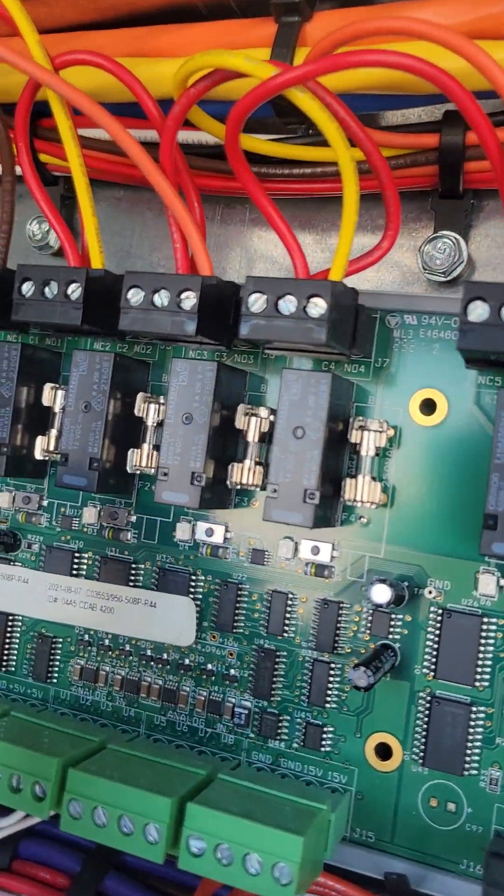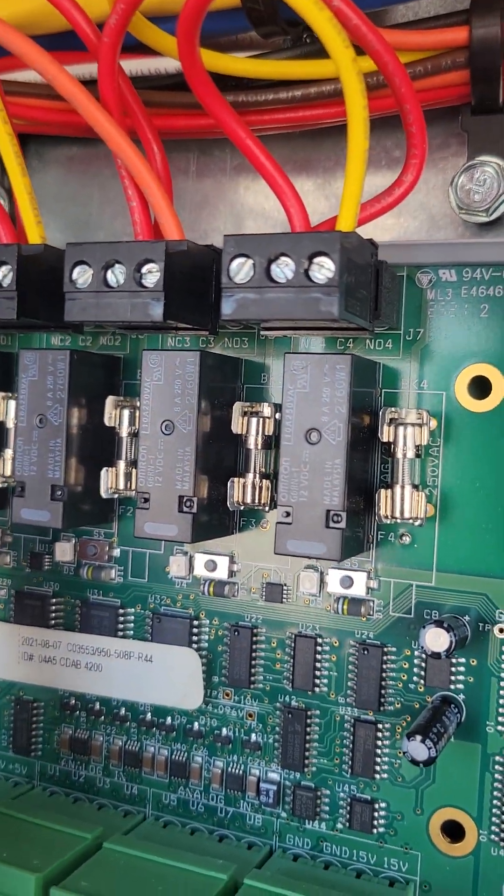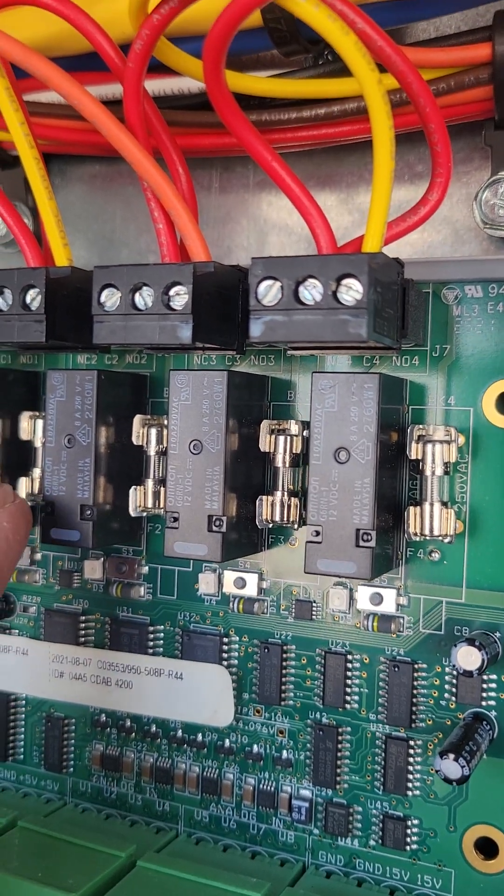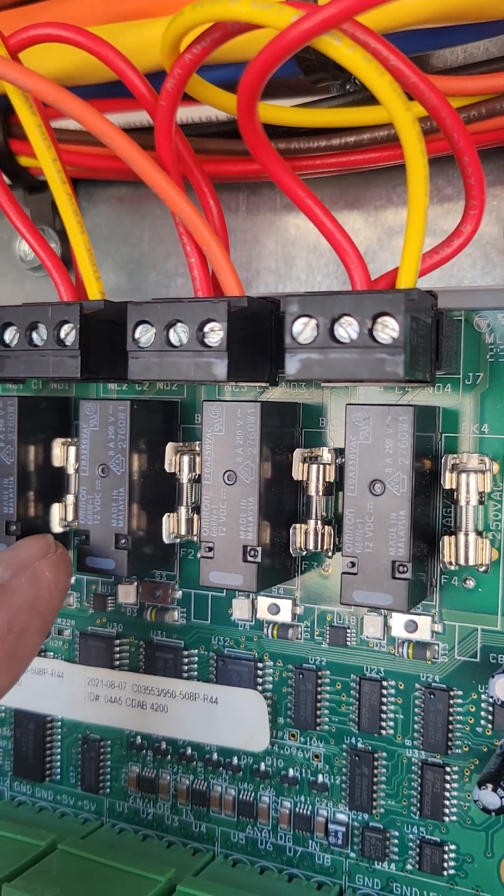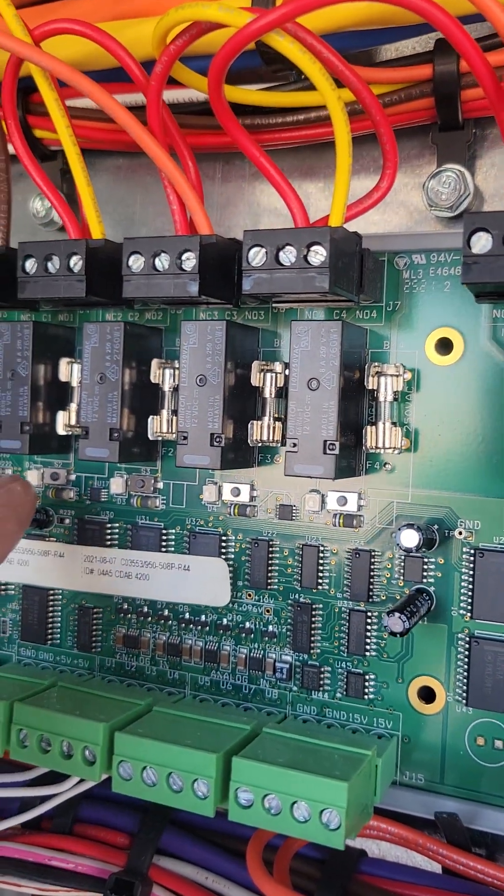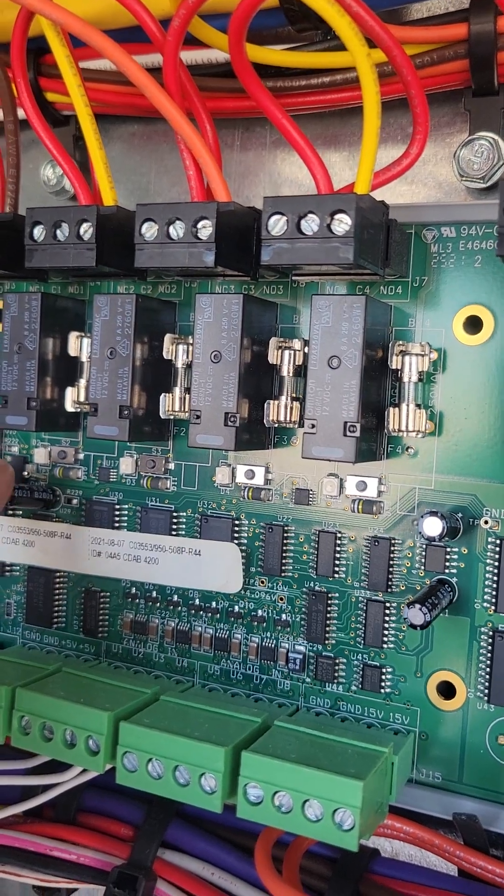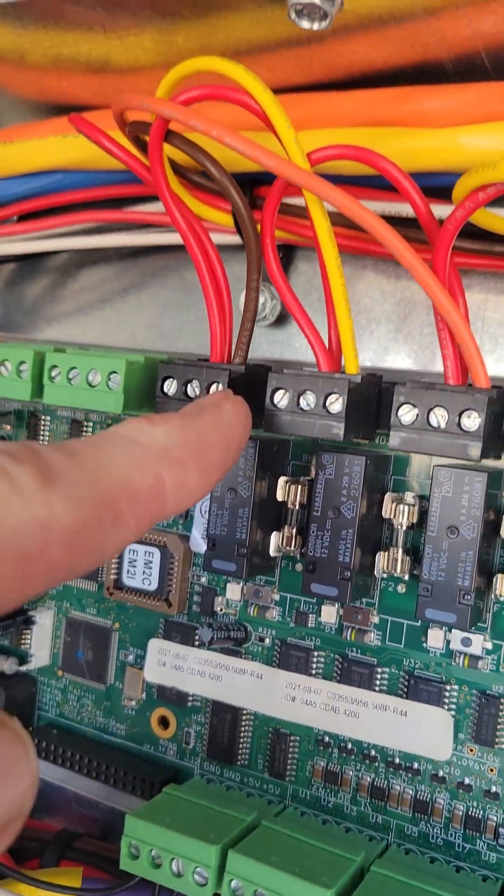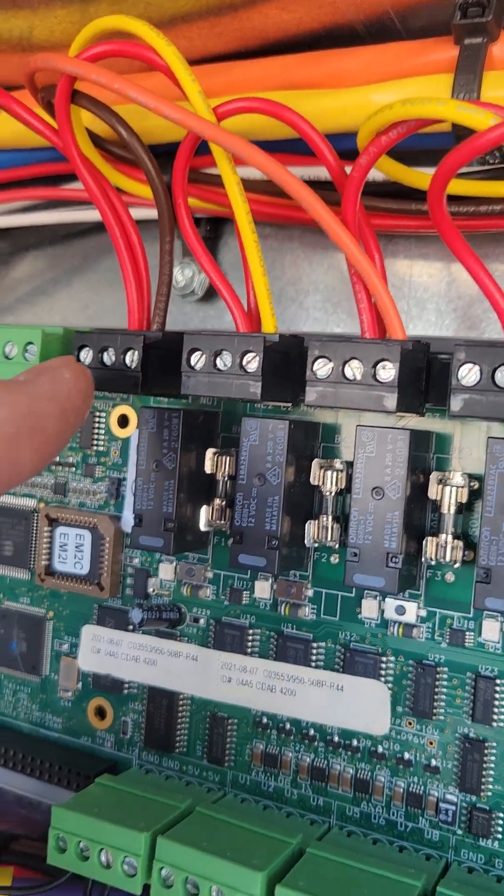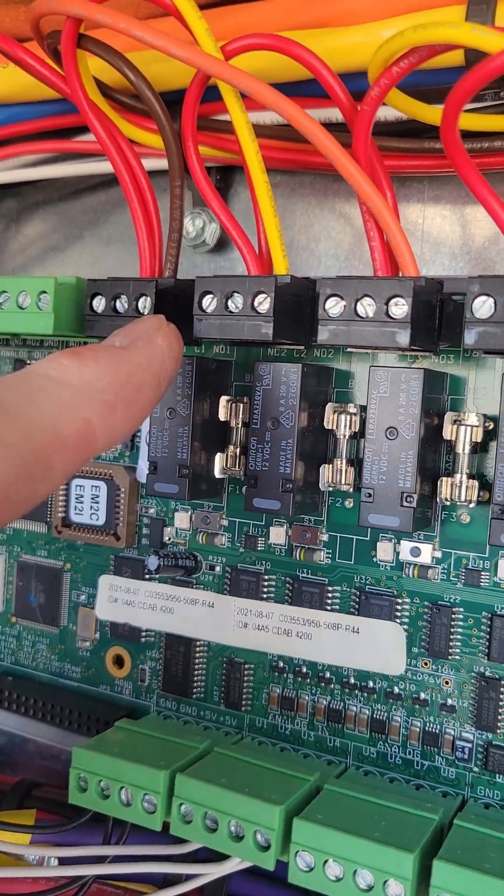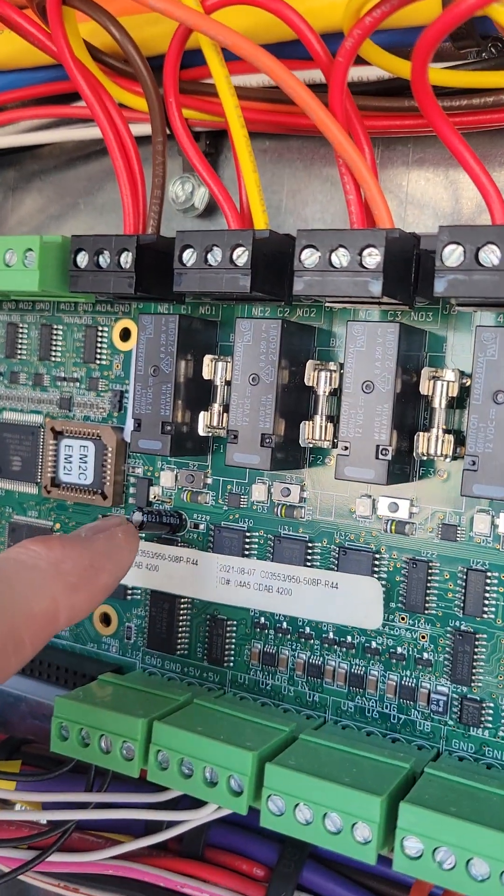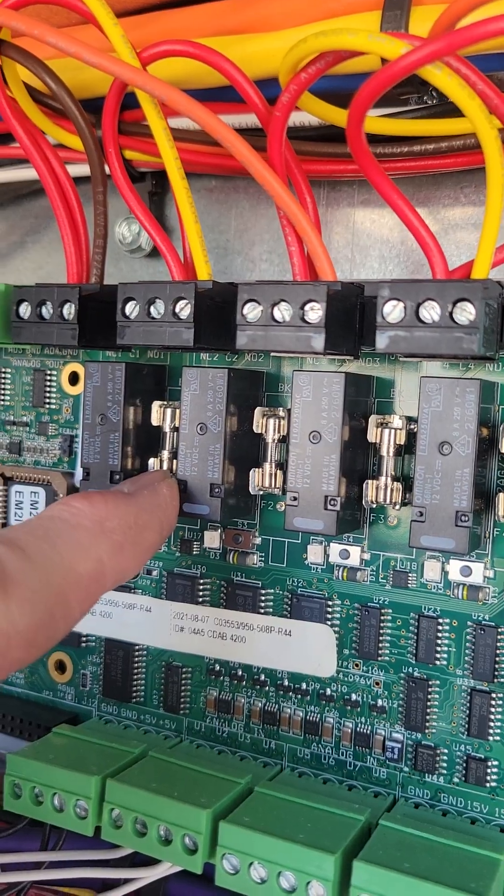And these outputs are also fused. So I have at times found blown fuses on these outputs. So you'll see the little light is on, but there's nothing coming out. You'll measure that output wire and say, hey, why is there nothing here? You got 24 volts coming in, you got nothing coming out, the light is on. More than likely that fuse is blown.